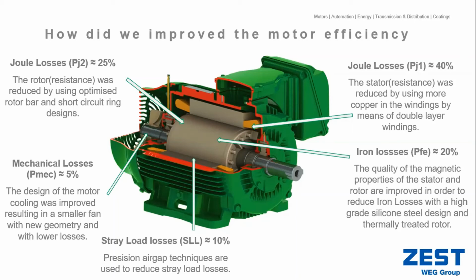We also look at the iron losses inside the electric motor rotor, the rotating part of the motor. The only way to improve that is by improving the laminations used in the motor, using the highest grade of silicone steel design we can.